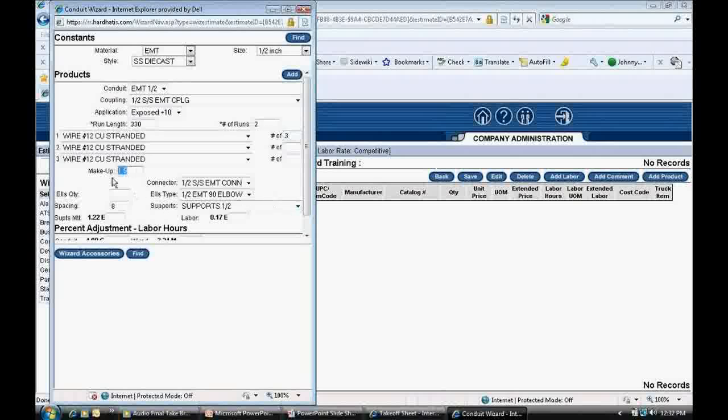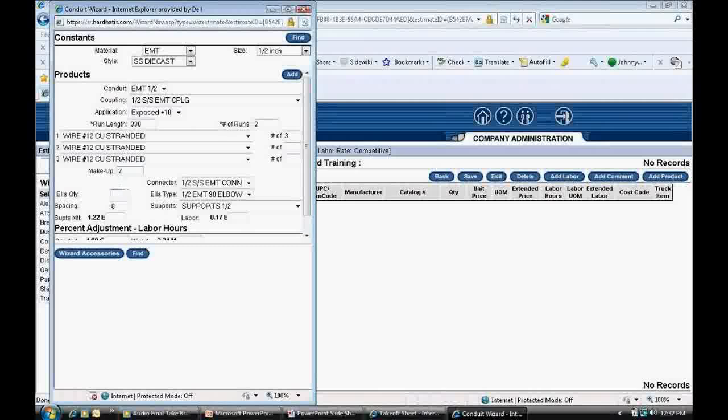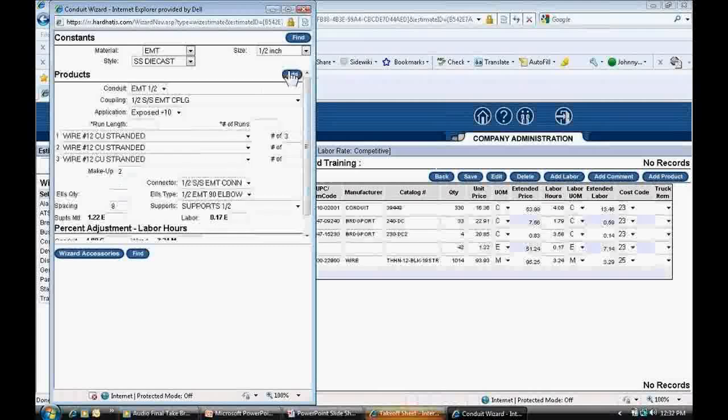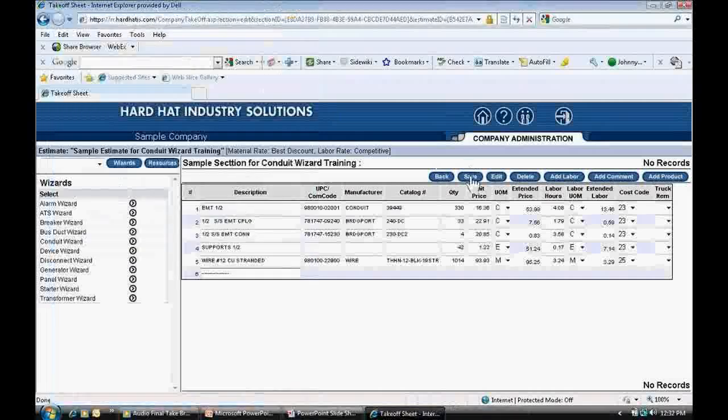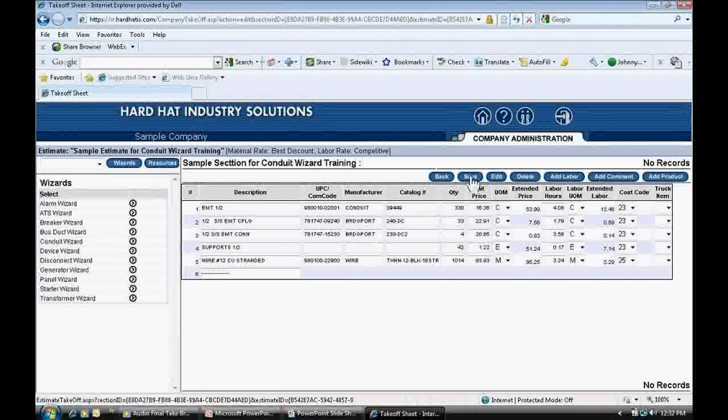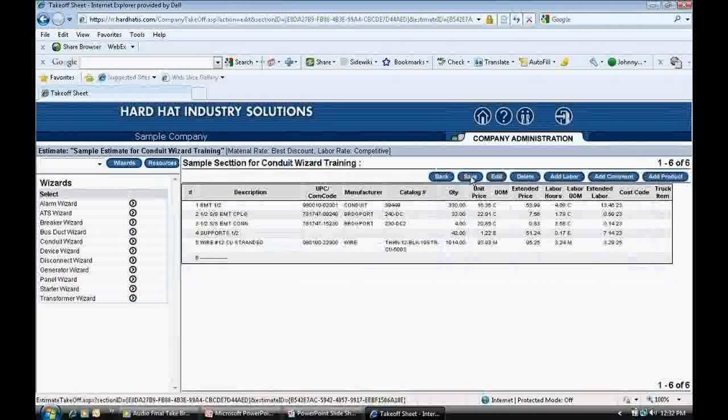I check the makeup box and enter 2 feet for makeup length. I do not enter elbows for branch circuit conduit because they're field bent. Next, at the top of the pop-up, I click the Add button. This will populate the materials to the takeoff sheet. Next, I click the Save button at the top of the page to save my work.